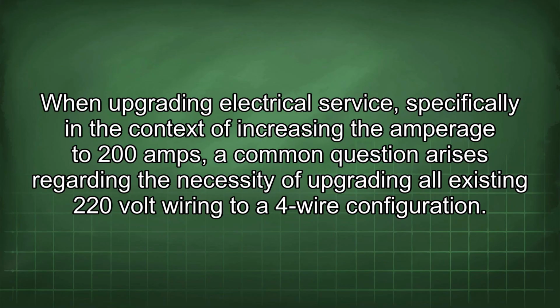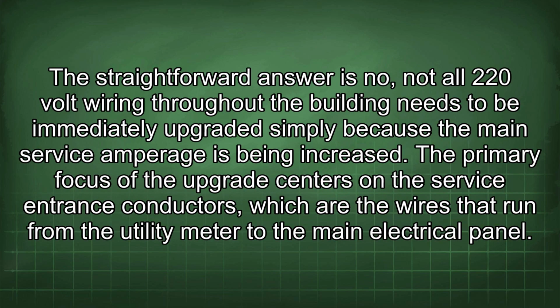When upgrading electrical service, specifically in the context of increasing the amperage to 200 amps, a common question arises regarding the necessity of upgrading all existing 220 volt wiring to a 4-wire configuration. The straightforward answer is no.